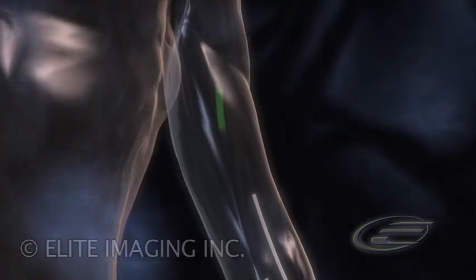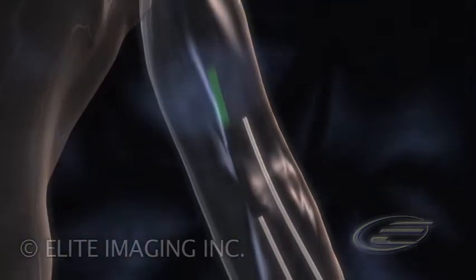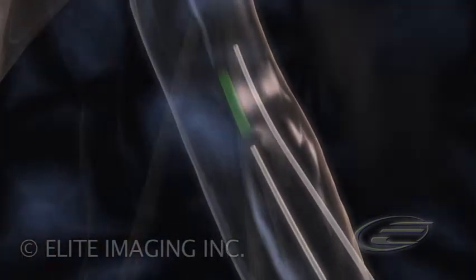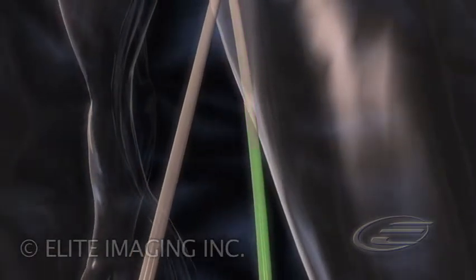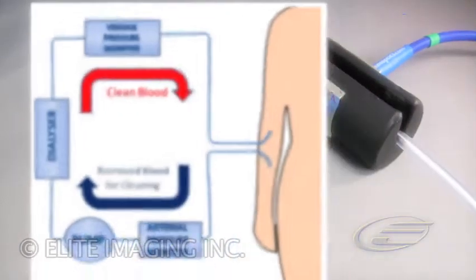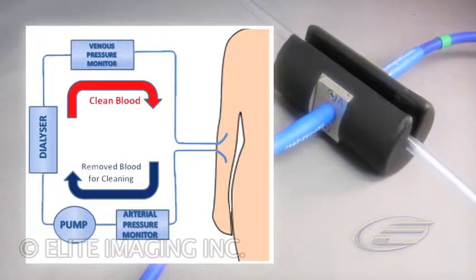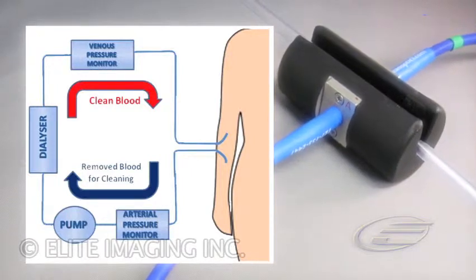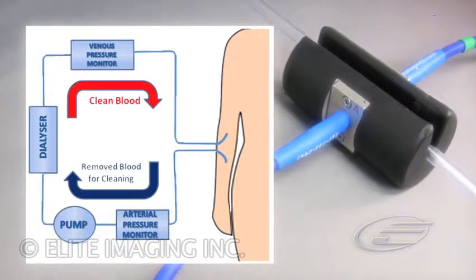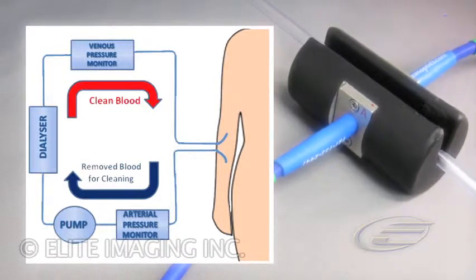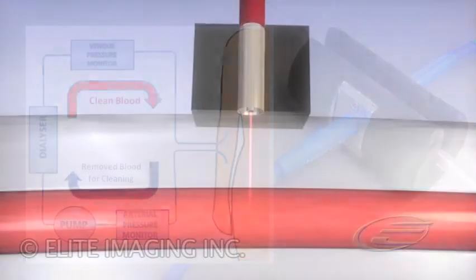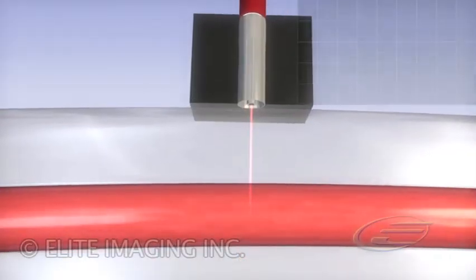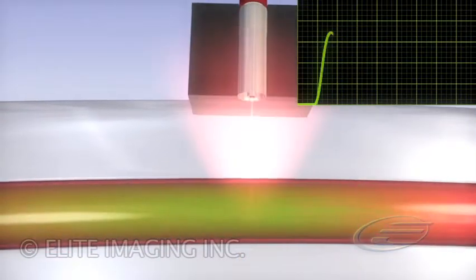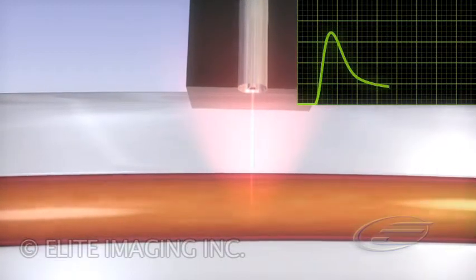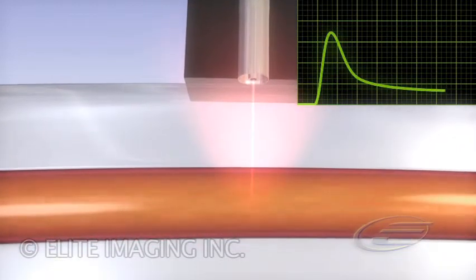The dye travels through the body, enters the arterial network, where it is detected on the arterial side of the dialysis circulatory path. The device is an optical element comprising 2 optical fiber cables and a receptacle for the circulation line. This device is self-calibrated using a novel patent-protected method. The dye that flows with the circulating blood is illuminated by a near-infrared light attached to the probe. The light causes the dye to fluoresce. The fluorescence intensity is recorded.